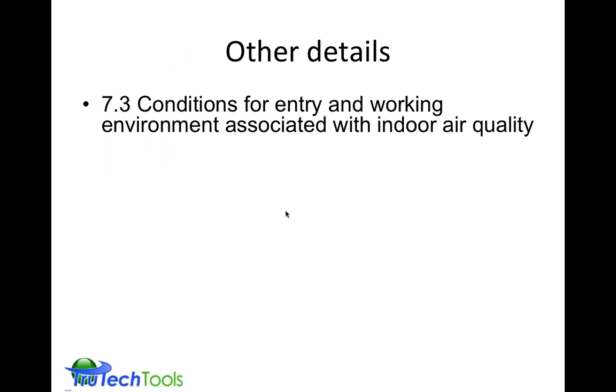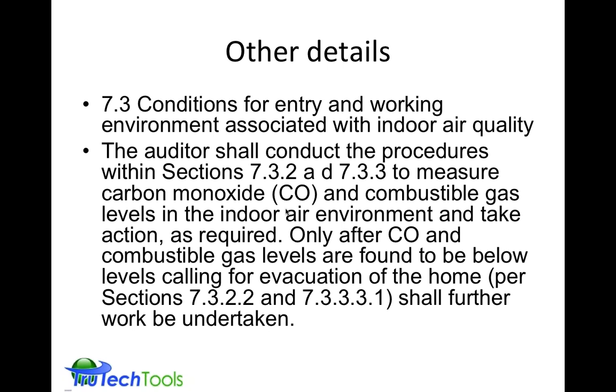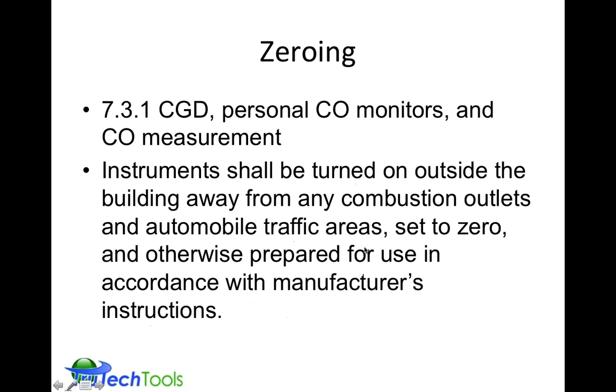The other details for use of these test and measurement products, the conditions for entry and exit, are associated with indoor air quality. You must be able to measure the CO levels and take action if required. And only after the CO and combustible levels are found to be basically safe, or found to be below the levels calling for evacuation, should you do any further work. So there's a stop work condition built into the standard.